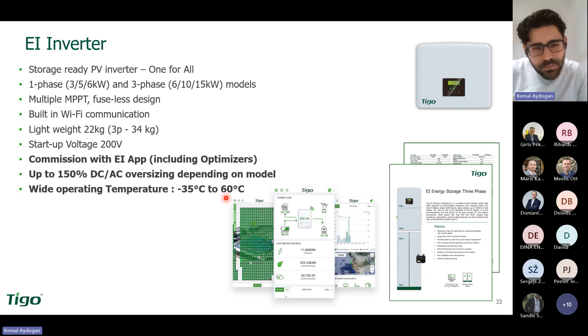On single phase, it has 90 volts starting voltage. On 3-phase, it has 200 volts starting voltage, and it can have a really great amount of DC to AC oversizing. Most importantly, it can work from minus 35 degrees to plus 60 Celsius degrees. So it has a really high operating range.